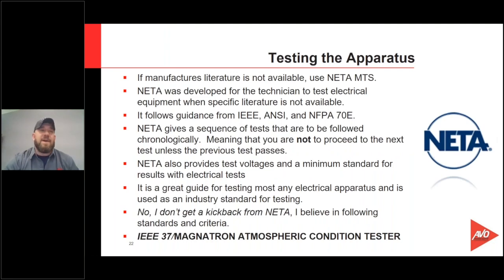More on testing the apparatus. If the manufacturer's literature is not available, use NETA MTS, International Electrical Testing Association. MTS stands for Maintenance and Testing Standards. So like I told you before, at AVO we teach maintenance and safety, so this is the standard that we follow: NETA MTS. We get neck deep into NETA in our classes, but like I said, with interrupters, I have my guys go right into the manufacturer's books.